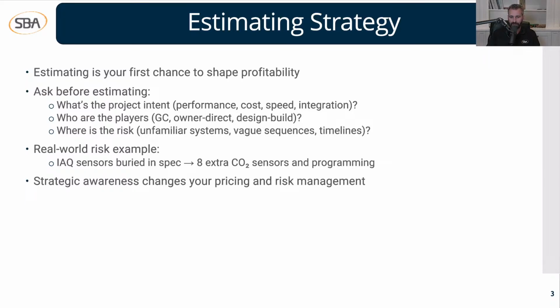If we hadn't caught that, we'd have paid for the material cost on the CO2 sensors, which are very costly, and you'd need 8 of those. Think about all the programming, startup, graphics, and software configuration. For 8 sensors, that time adds up a lot. So making sure we understand the sequence and read every single line helps eliminate some risk there.